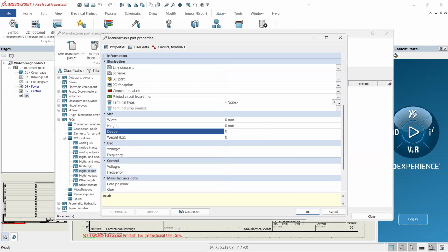It will scale it automatically to our sheet scale based on this information. And the reason it's better to use the CAD model is that Allen Bradley and other manufacturers, it's not just their fault, tend to ignore things like locking tabs that might add a couple of millimeters if you think about it. So this is a bounding box of the whole part, just a box that encompasses the whole part.